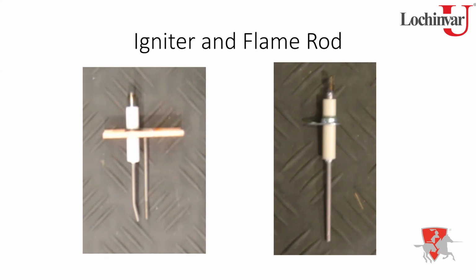You know, another way to check your flame signal to make sure you've got a strong flame is simply to go back to that sight glass and make sure that you've got a nice strong blue flame, not pulsating like we were talking about earlier, because like we just said, the control is not going to tell you the DC microamp flame signal that it's receiving. And you'll see later, it just says we have a flame or we don't have a flame. It's yes or no. Yep.